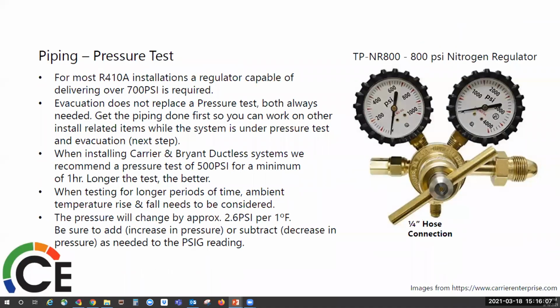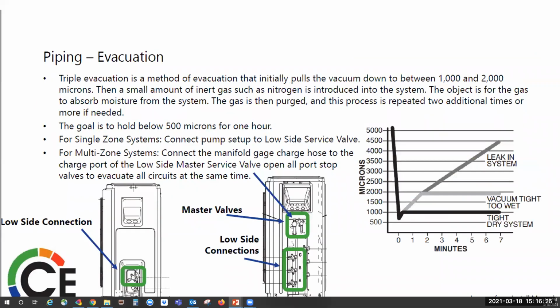Pressure check is always recommended. You go up to 500-600 PSI minimum for an hour. See if it leaks. Remember, an evacuation does not replace the pressure test. Triple evacuate the system, pressurize it. When pulling a vacuum, you want to consider your moisture level outside.